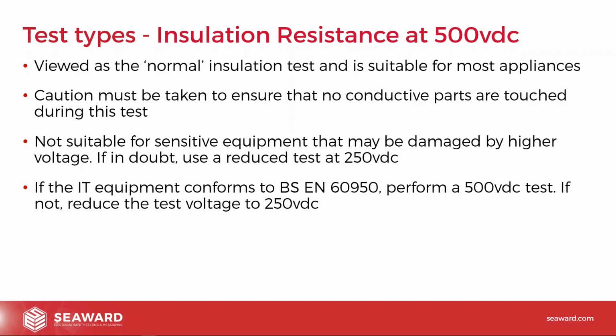If we've got equipment that's sensitive or surge protected, generally we wouldn't want to carry out the 500-volt test. We'd probably go down to 250 volts just for that reason. For surge protected equipment, obviously it sees 500 volts as a surge, so you will get some very funny readings if you test at 500 volts.